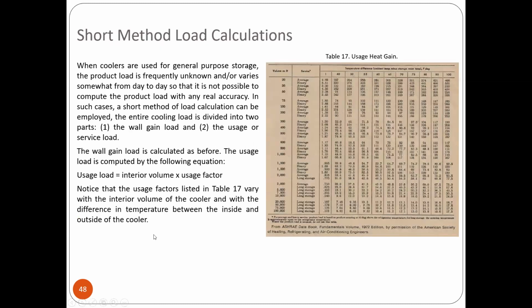Short method calculation. When coolers are used for general purpose storage, the product load is frequently unknown and varies somewhat from day to day, so that it is not possible to compute the product load with any accuracy. In such cases, a short method of load calculation can be employed. So, when you don't have products yet, you can't identify the products. So, we have the wall gain load and the usage or service load.